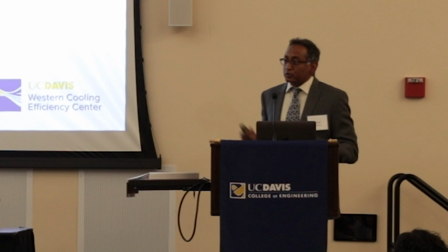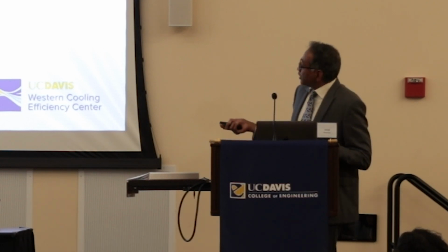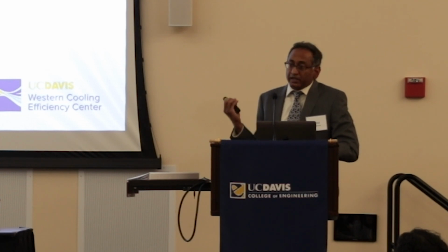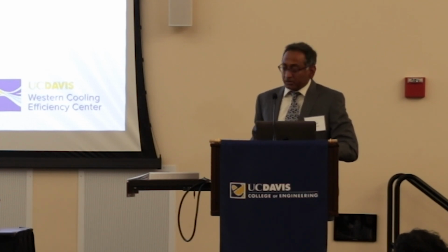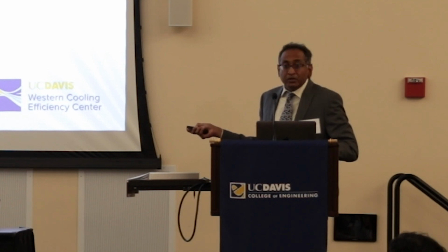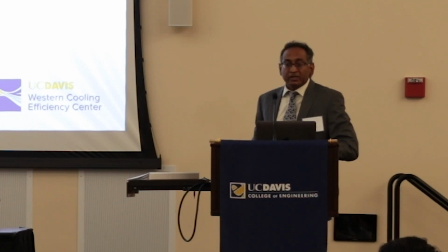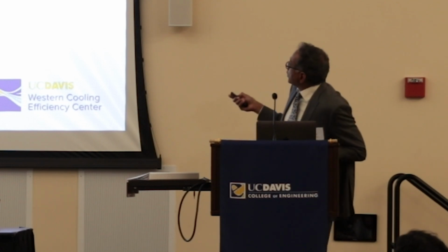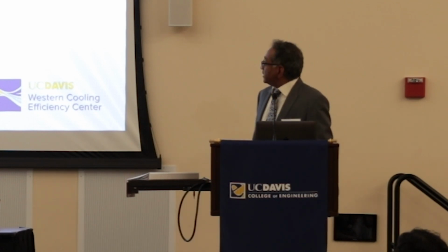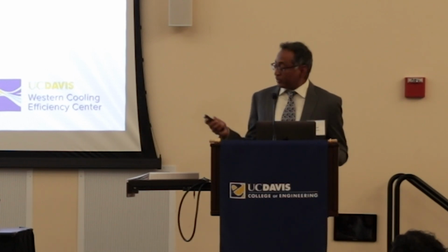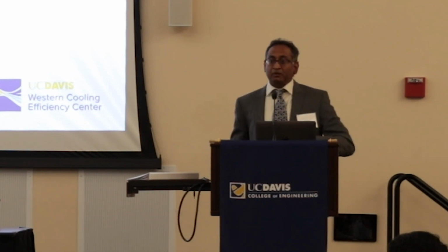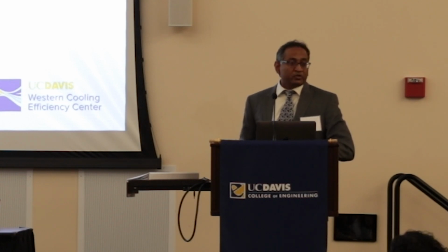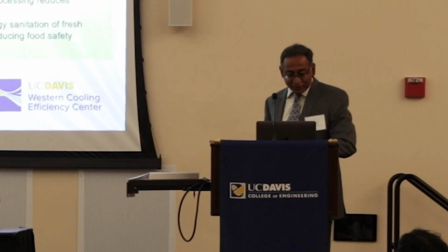You still have a delta T to transport heat. You don't need to chill the building down. That's the idea. So if you can get down the electrical energy used for cooling from 40% to 5%, that's the challenge given to us by ARPA-E. You can have tremendous savings. You're going from 390 terawatt hours to 253 terawatt hours doing that. That's equivalent to removing a dozen power plants from the grid. So our concept is shown here. It's a highly dense modular data center. So imagine a 40-foot shipping container volume, and imagine having 1.5 megawatts of compute in it. That's the kind of density we're talking about for the future of data centers. Too much to talk about here, so I'll stop here and be open to questions.